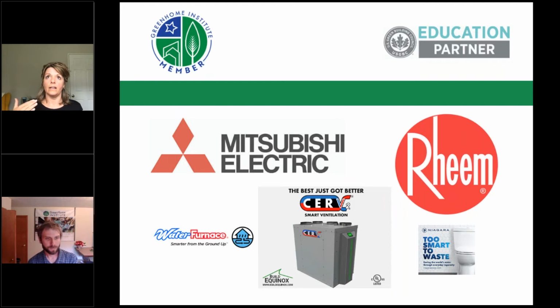Right. So whatever the homeowner's budget will allow, but if you add dedicated dehumidification, you're guaranteed to get to that relative humidity set point. And then you let the air conditioner worry about that sensible load and remove water while it's doing it. But the whole point of building our tighter houses is not to run the air conditioning, the HVAC system, as much. It's to lessen those sensible loads. Now we just have to have something to think about the water. And it's probably far more energy efficient to run a 5-amp dehumidifier. Even when the AC systems ramp down and use less energy, they're still using more energy than that.